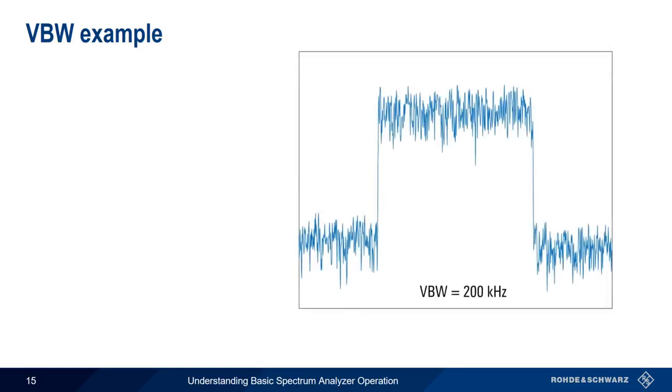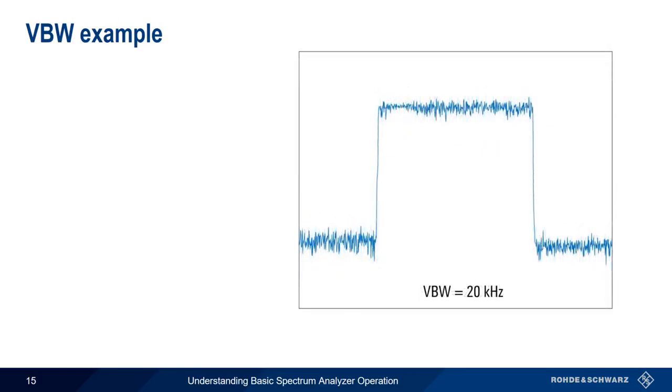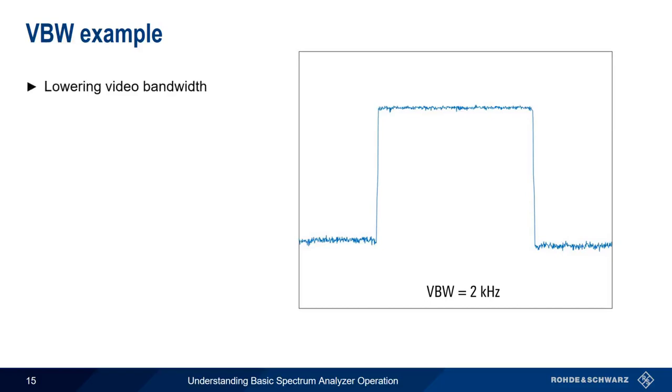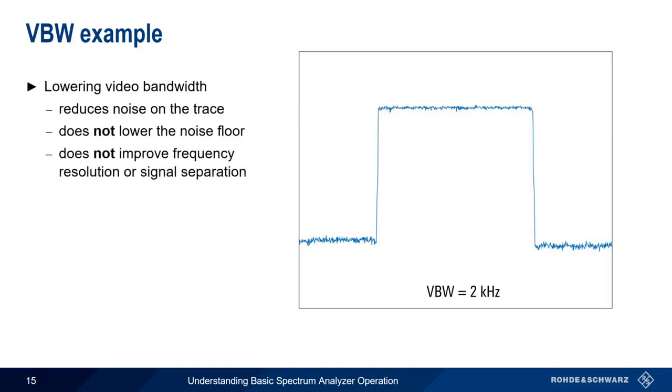Let's take a closer look at an example of what happens as we lower video bandwidth. At a video bandwidth of 200 kHz, we can see a fair amount of noise on our signal. This noise is reduced when we lower video bandwidth to 20 kHz, and decreases even further when video bandwidth is lowered to only 2 kHz. Lowering the video bandwidth only reduces the noise on the trace. It doesn't drop the noise floor like resolution bandwidth, and it also doesn't improve our ability to resolve or separate closely spaced signals.